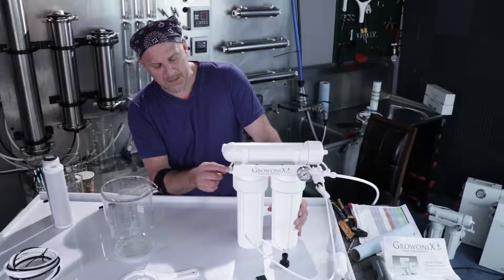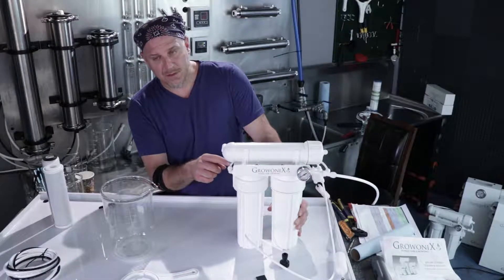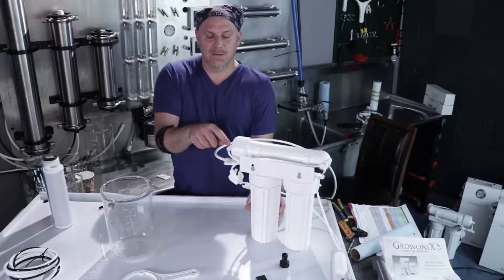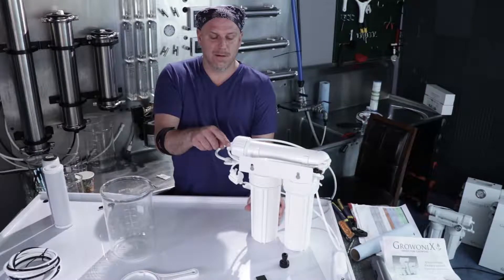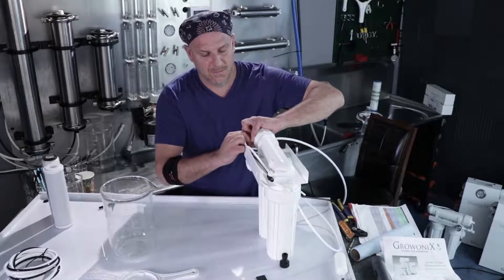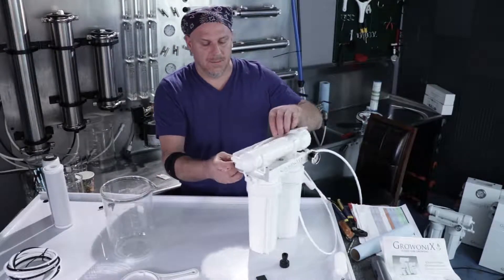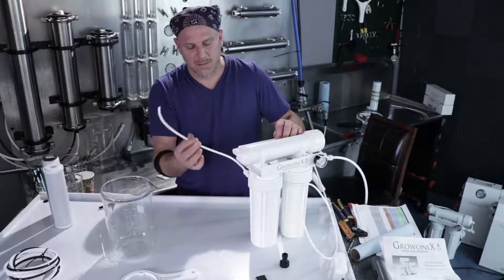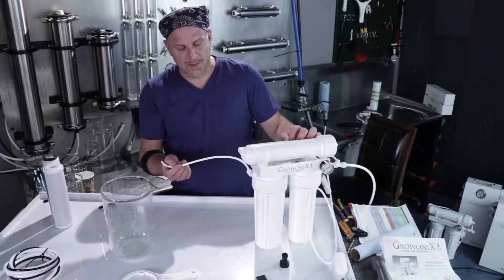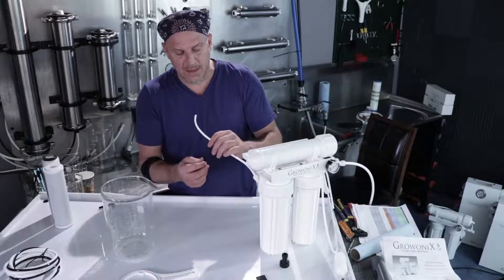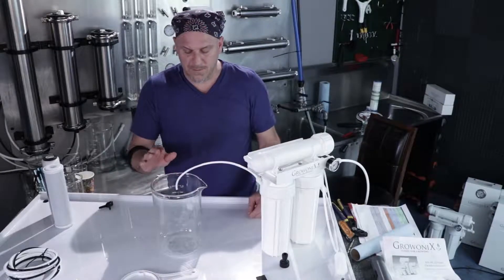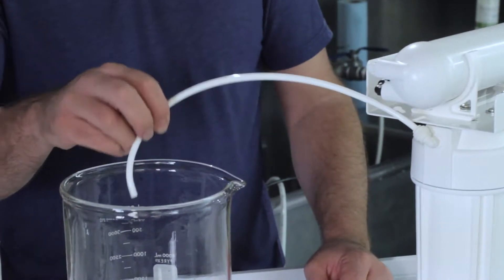So to flush the carbon what we do is we take the carbon output tube which feeds the input of the membrane on the other side of the filter. We're going to disconnect this tube and pull it back through right here. We're going to turn the water pressure on slowly and let this water flow out. We're going to flow into here so you can see it, this could flow down a drain.